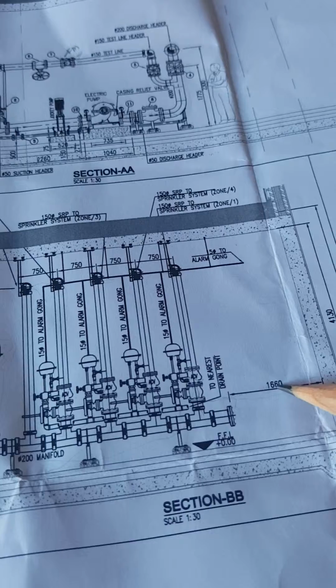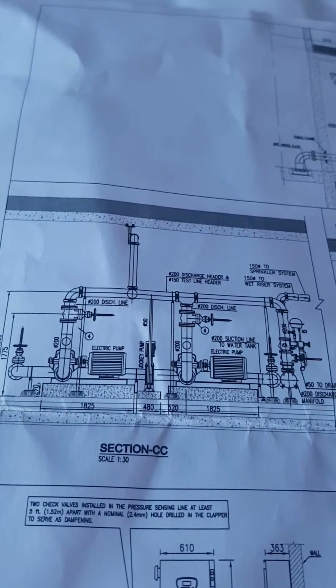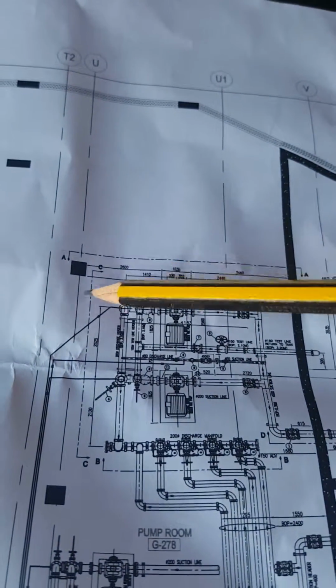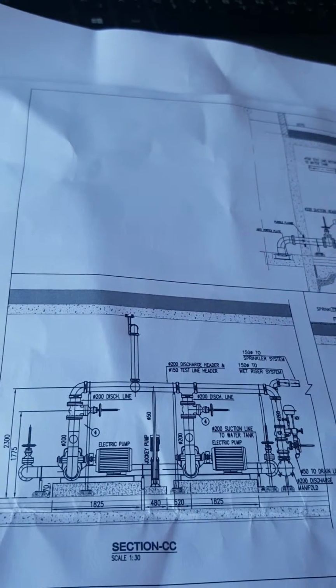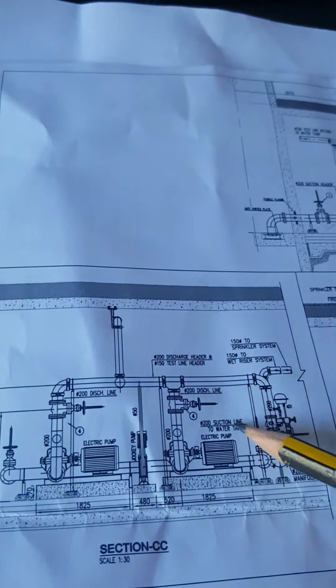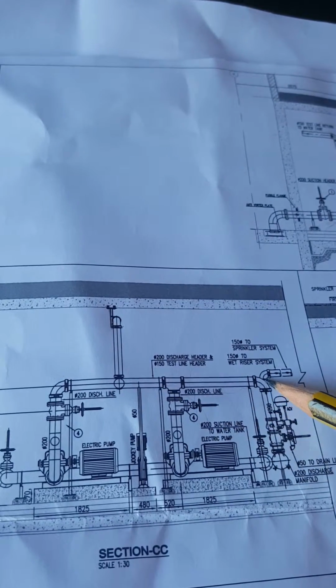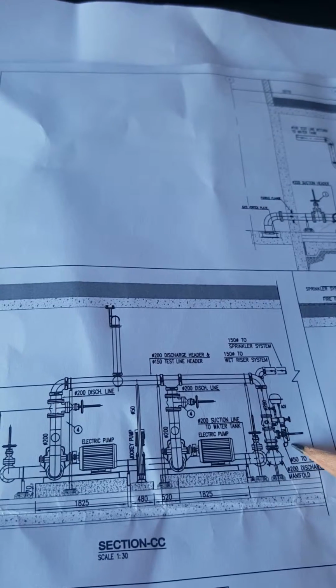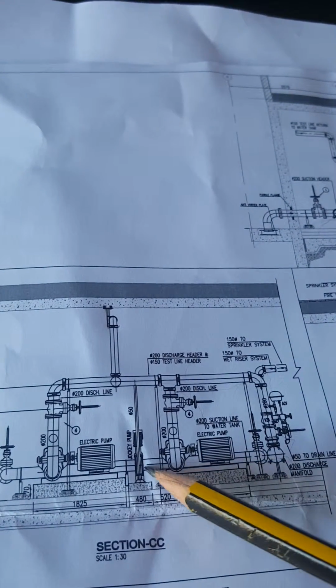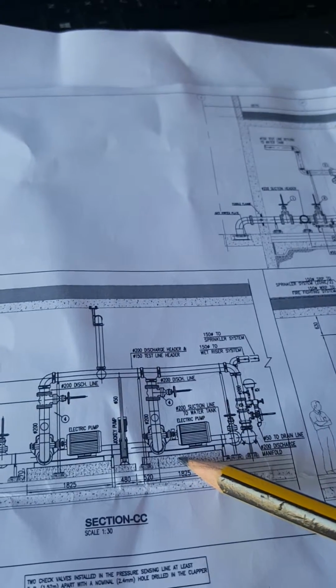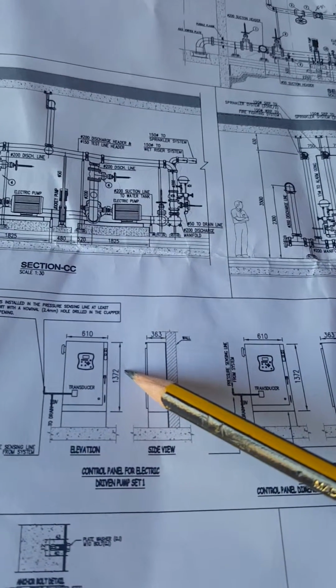In this case this is 1.6, and we've got some section CC. So what you will see in section CC is that it's cutting here, right here and there. So this is basically what you will see there. So there are electric pumps over there, this discharge header, there's a wet riser pump, this is the manifold, and there's a jockey pump and suction line with the gate valve, etc.